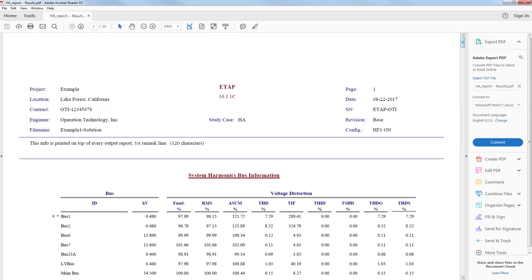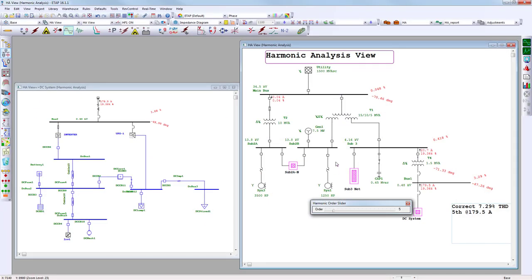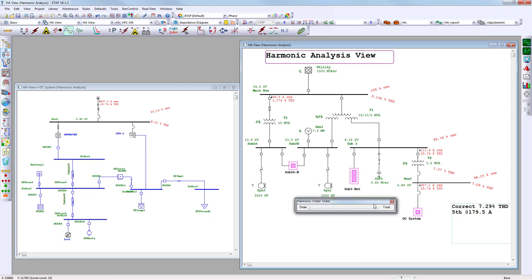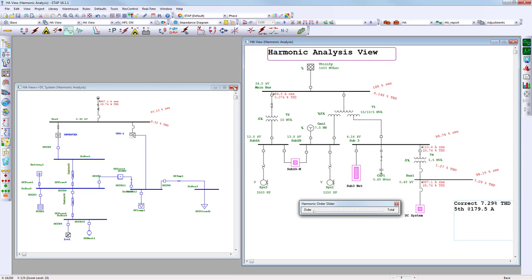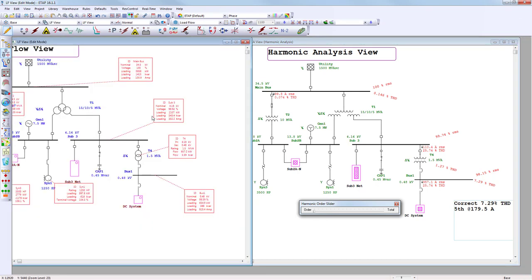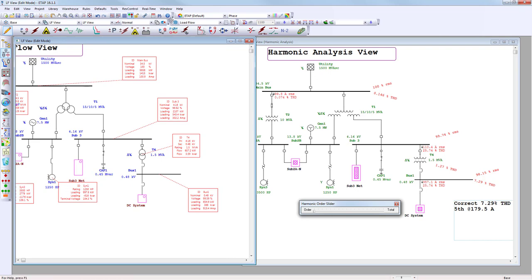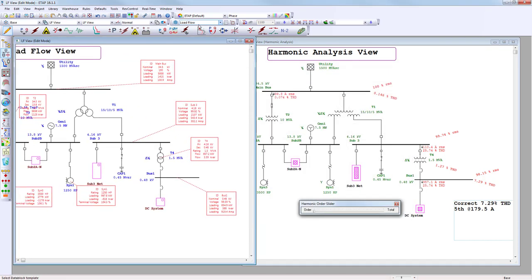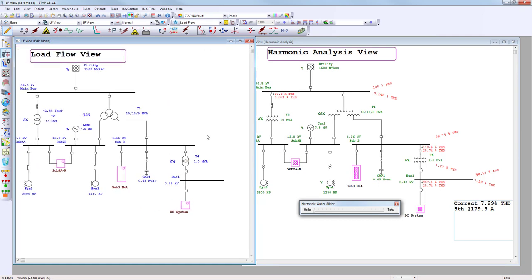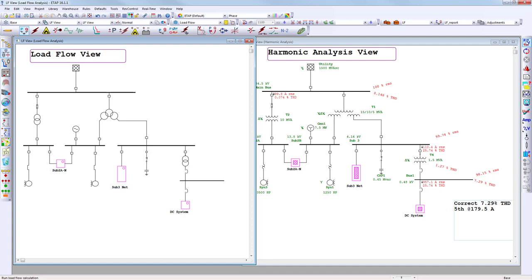The report is very comprehensive and would serve as an appendix to a harmonics study. Moving forward with the example, I want to display both the harmonic analysis view on the right — showing total harmonic distortion with the slider — and the load flow view on the left. Using ETAP's three-dimensional database, you can have multiple one-line diagrams representing the same single-line diagram, displaying different data simultaneously.